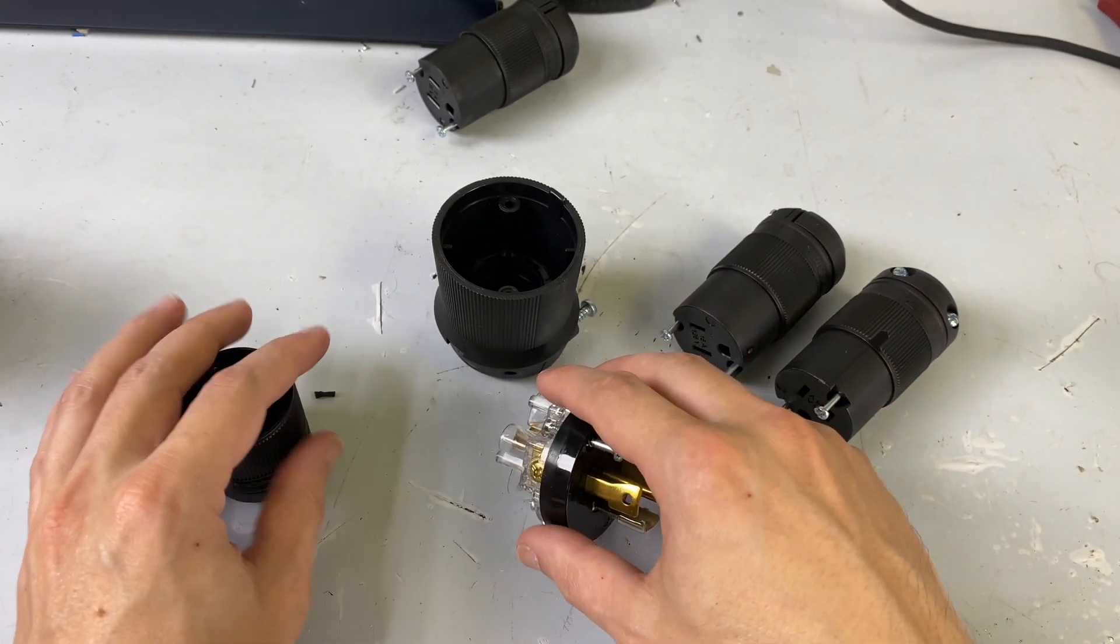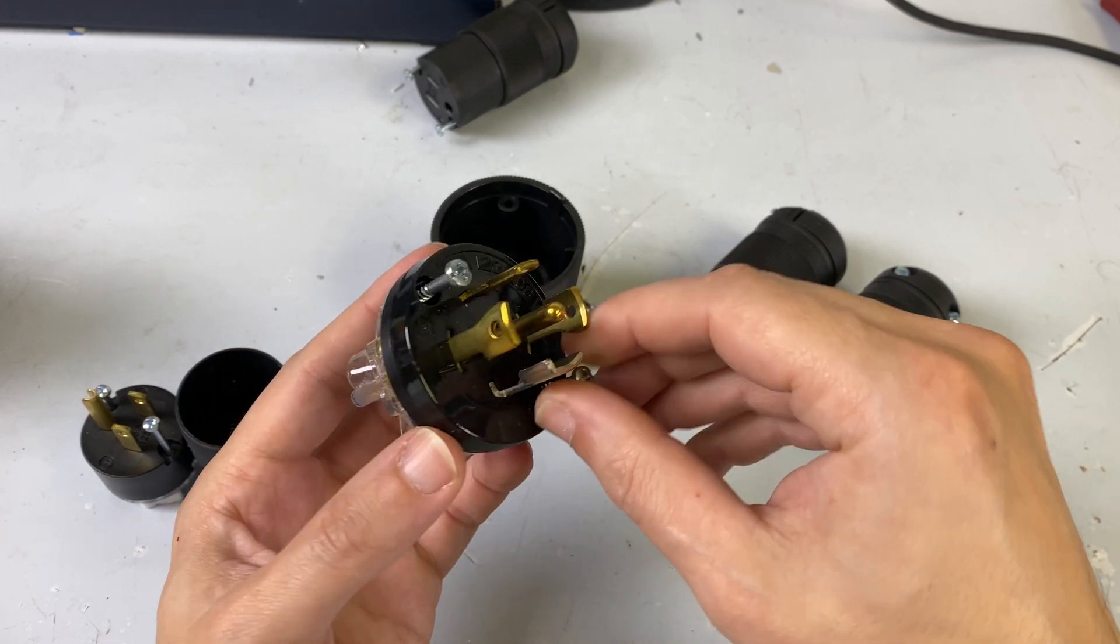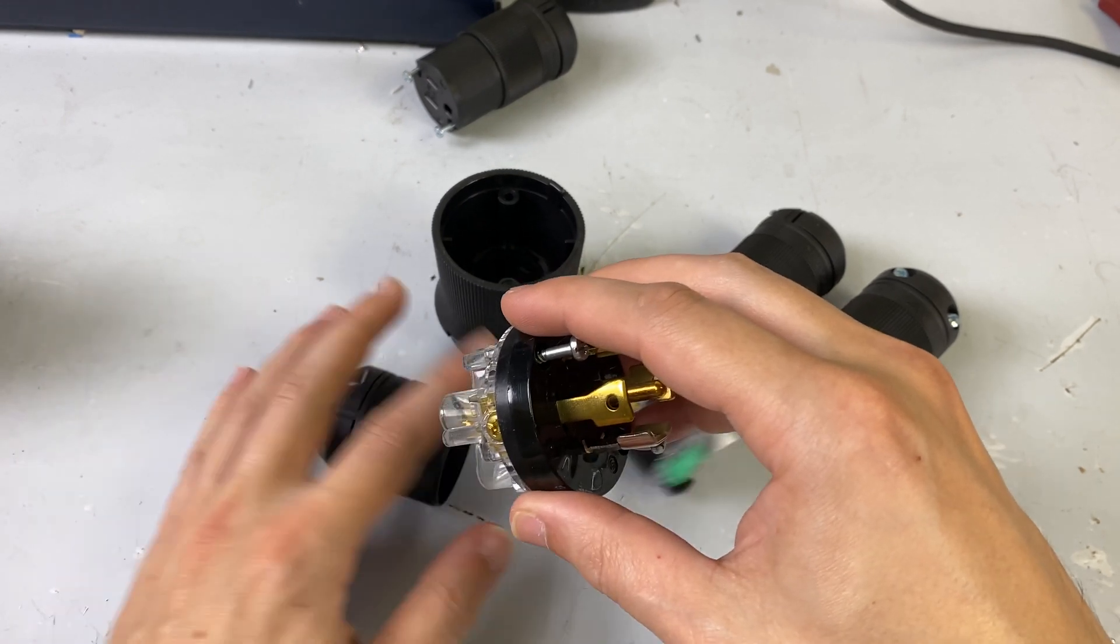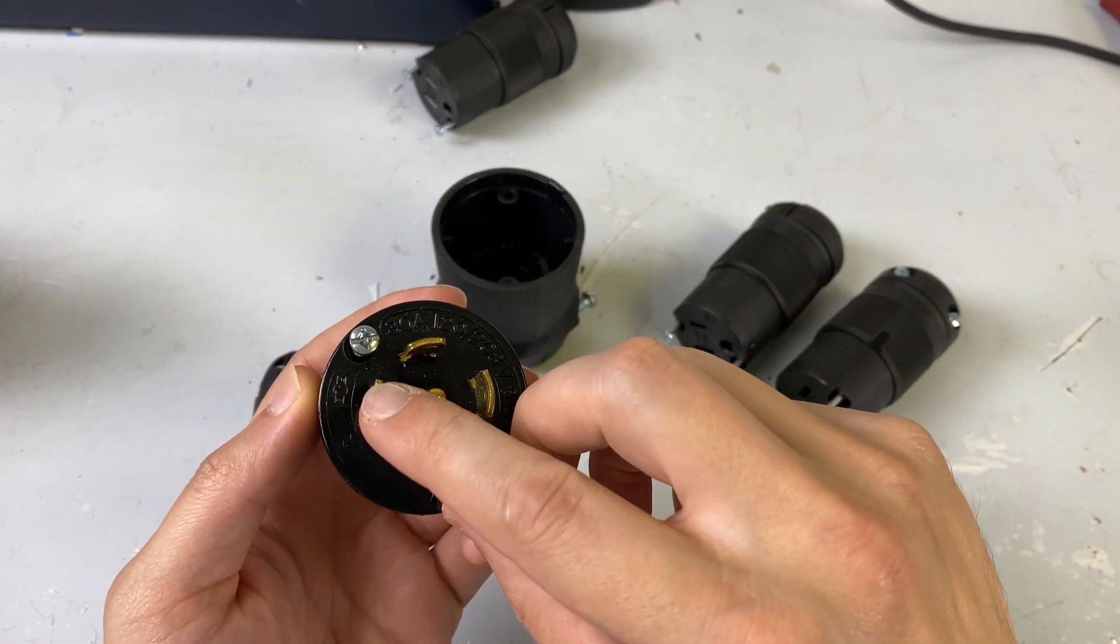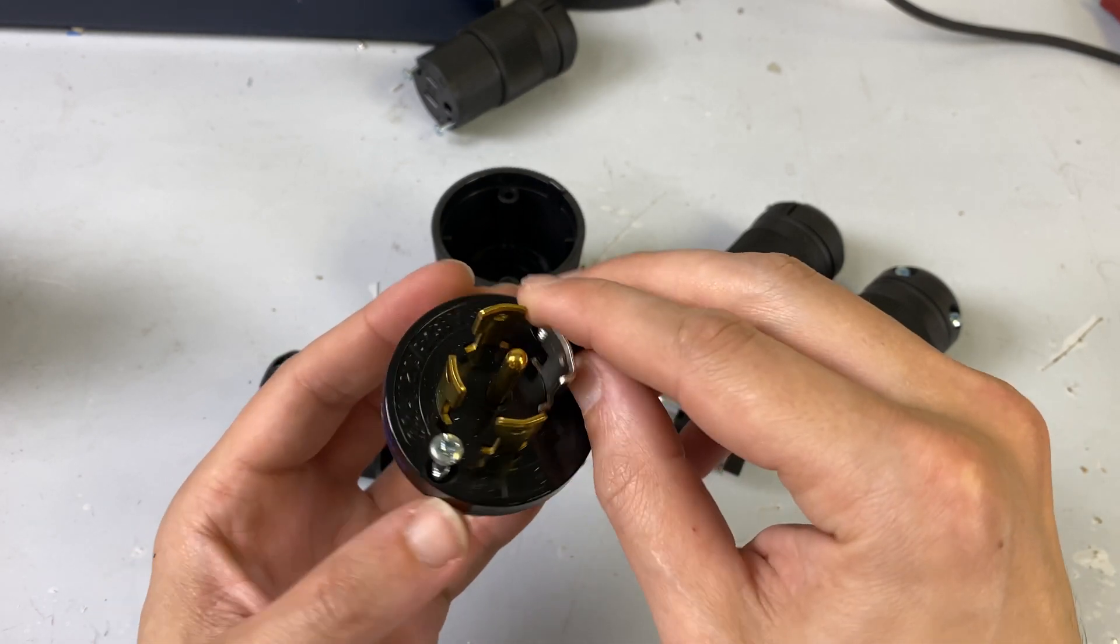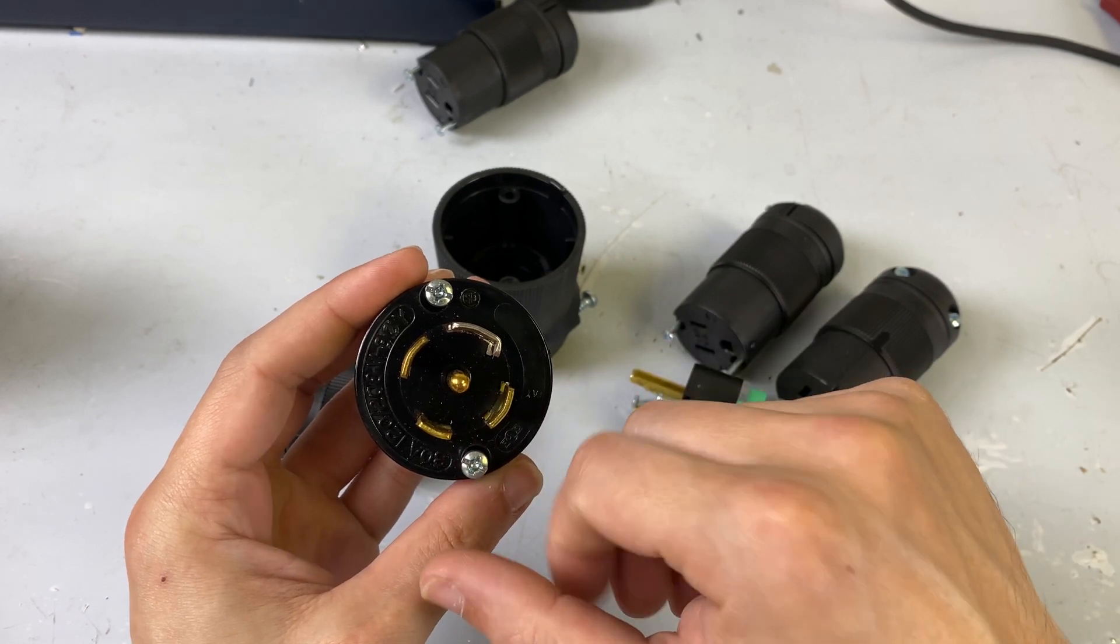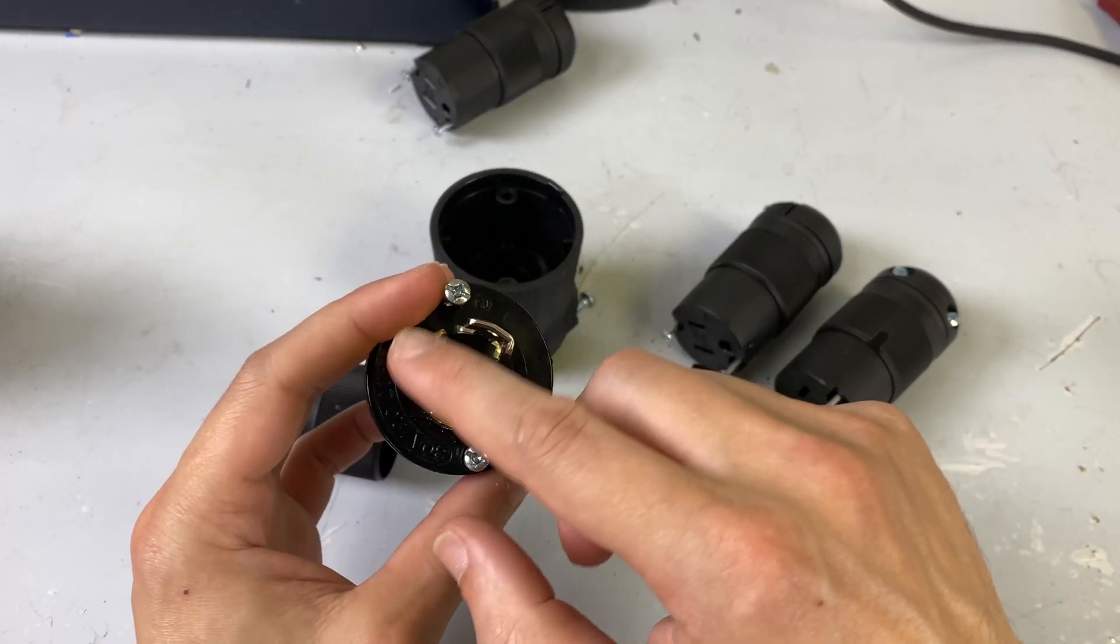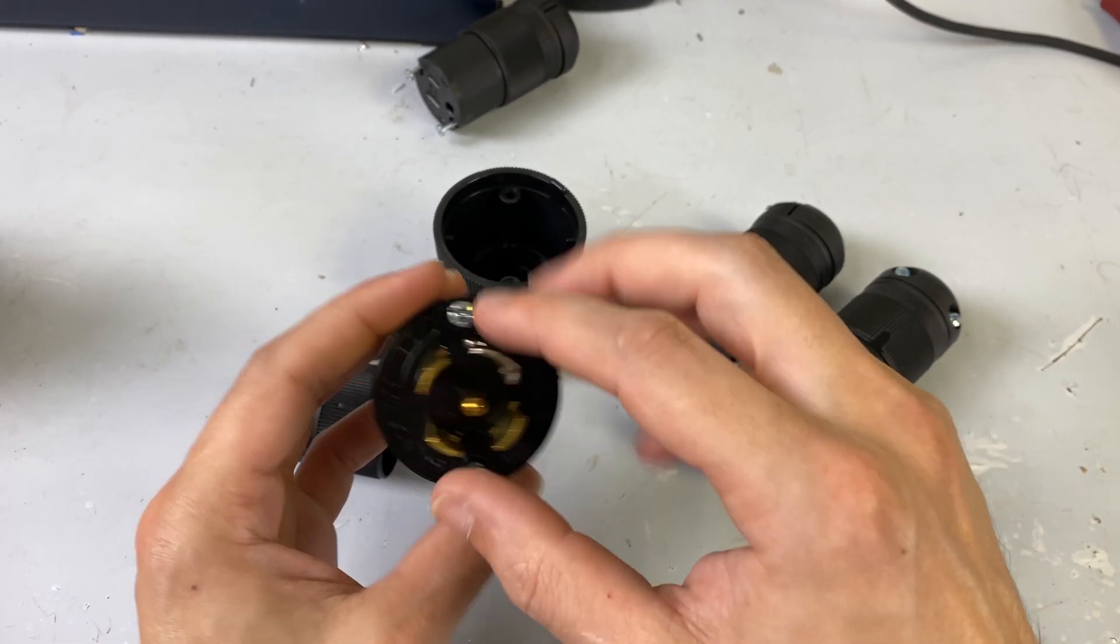So on a twist lock connector, or I should say a three-phase twist lock connector, you have three hots. So instead of one on this, you have three on this, so this is one, two, and three hots. You have one common neutral, and you have one ground pin that's in the center. So in this one connector, you have three hots, so three blacks essentially, a neutral, and a ground.